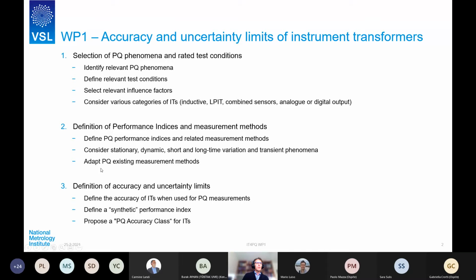And the basic idea is to adapt power quality existing measurement methods, and to select the proper ones, perhaps to adapt them where necessary. The third task is about definition of the accuracy and uncertainty limits, and that means to define the accuracy of the instrument transformers, so not of the power quality parameters themselves, but of the instrument transformers when used for power quality measurements. So we will try to define a synthetic performance index, and also to propose a new class of instrument transformers, or a new class definition, I should say, which is the power quality accuracy class.